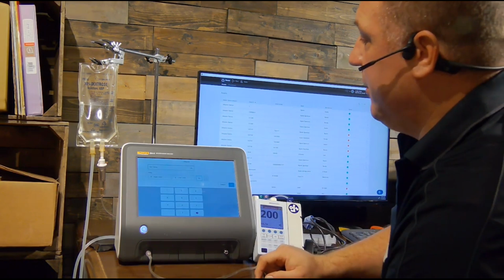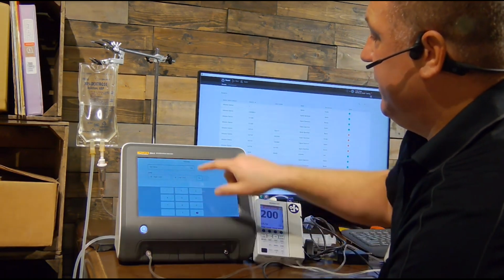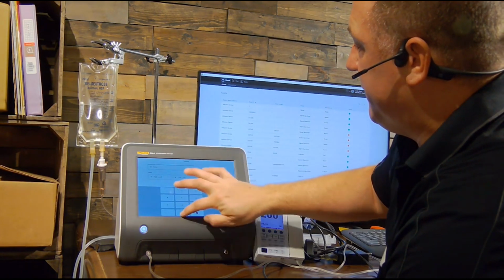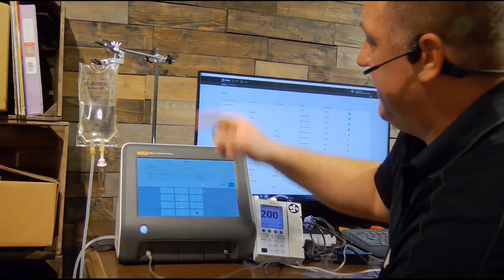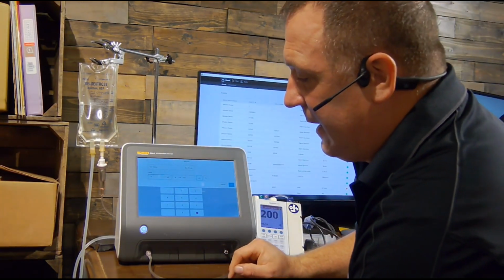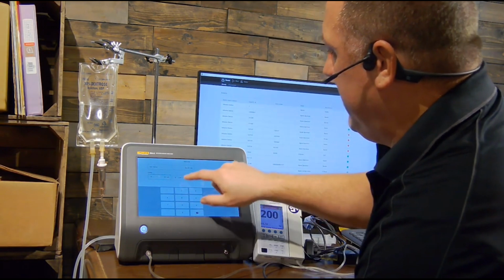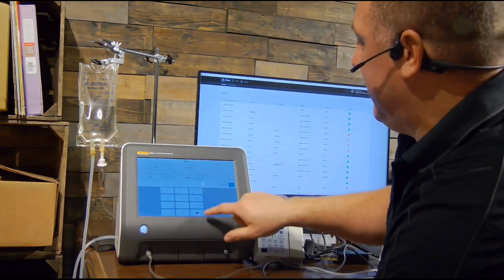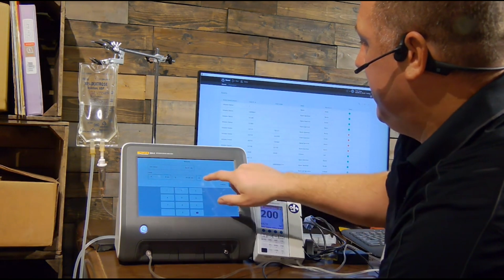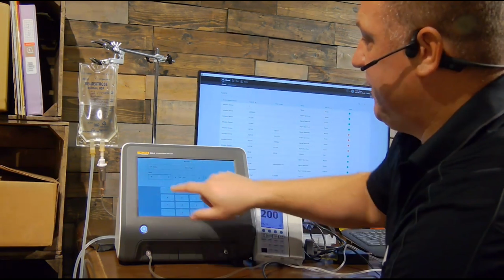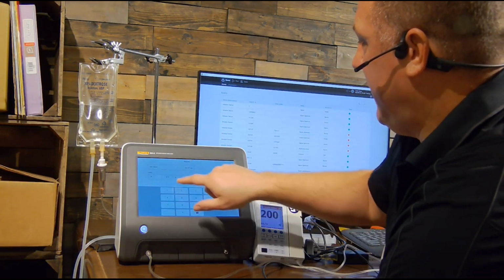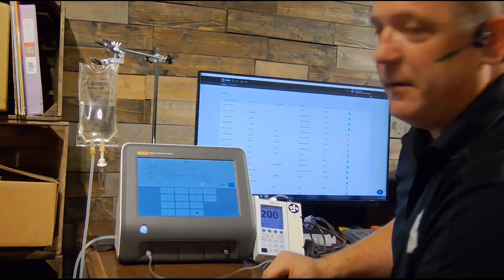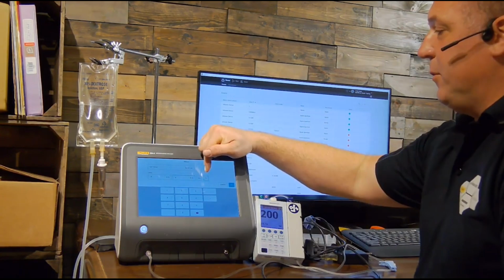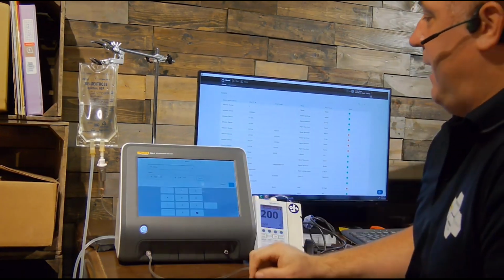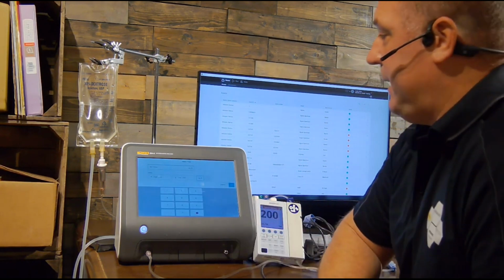So if I go to my volume, or any of these, I could set my expected volume. In this case, maybe it's going to be 50 milliliters. I can set my high limit, and maybe it's going to be 51, and my low is going to be 49. Or some people read in percentages. So I could take this back, let me just clear this out, and I'll make it 5%. So my high limit's 5%, and my low limit can be 5%. So again, I can do it by volume or percentage. All right, same thing with my time, and again with my mean flow.